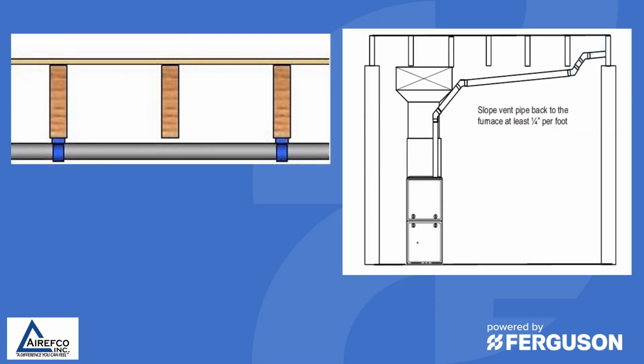When running the vent pipe to the outside, you need to make sure that you properly support the PVC venting as you run it through to the outside. Also make sure that you are sloping the vent back towards the furnace at least 1/4 inch per foot according to manufacturer specifications.